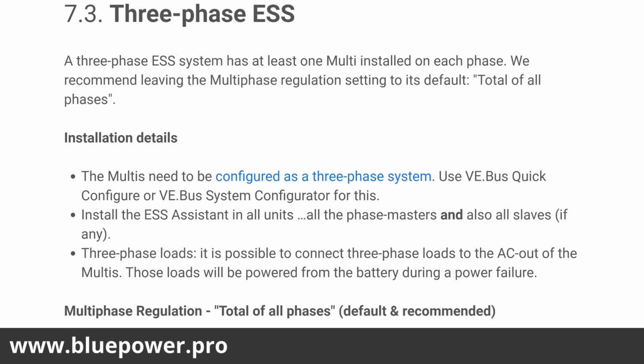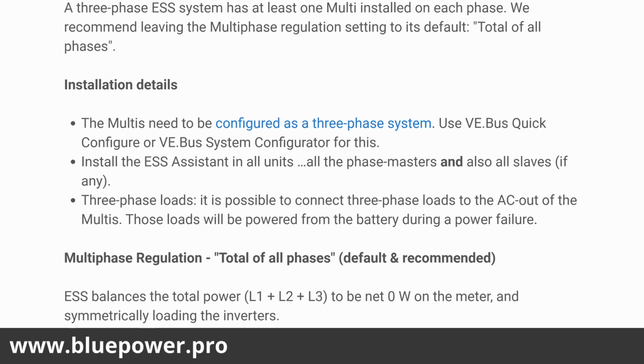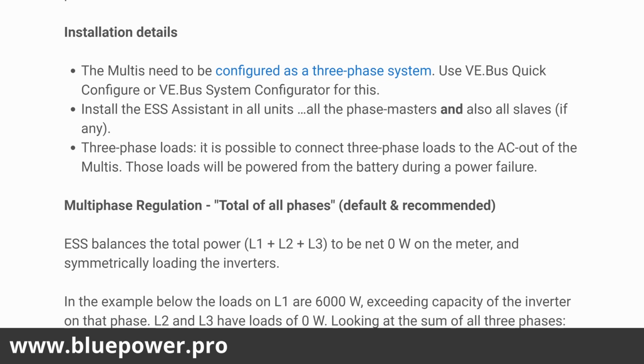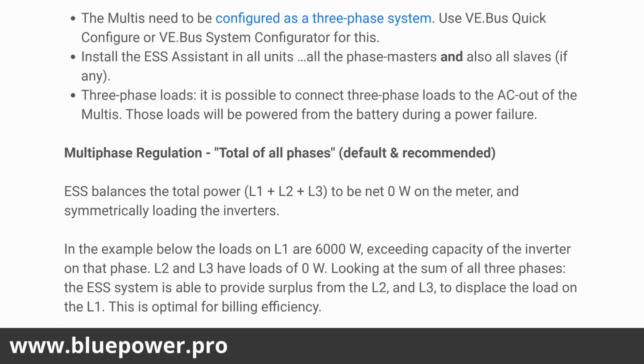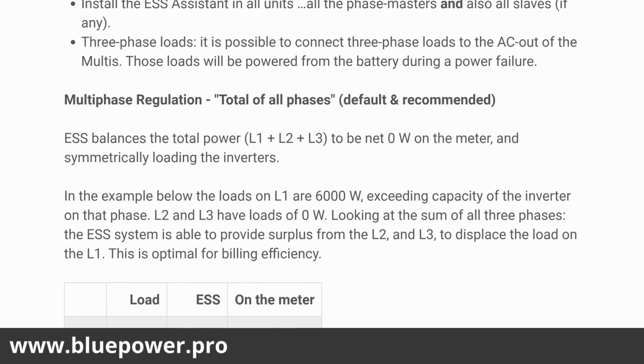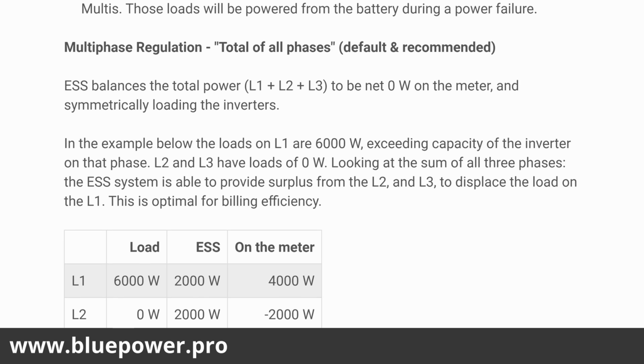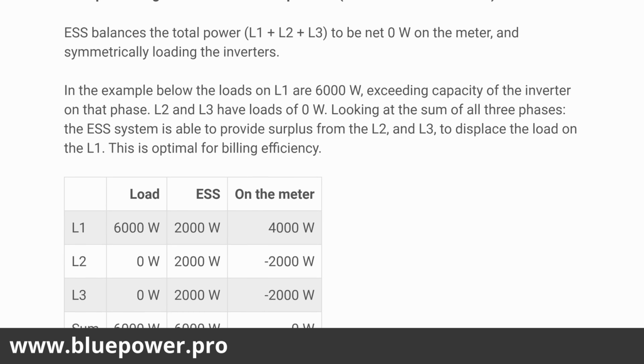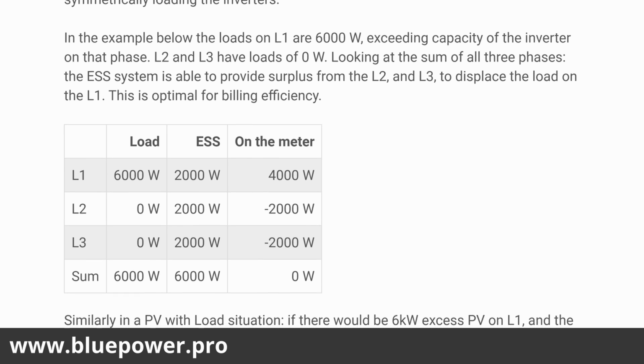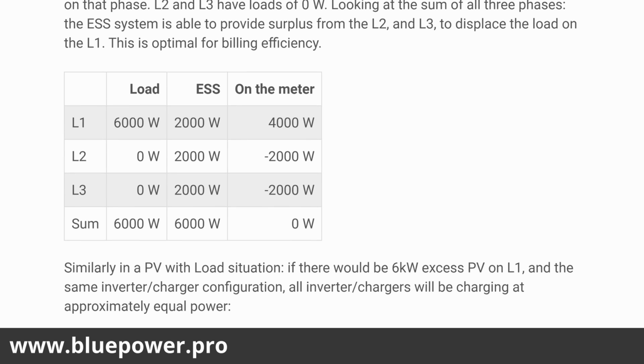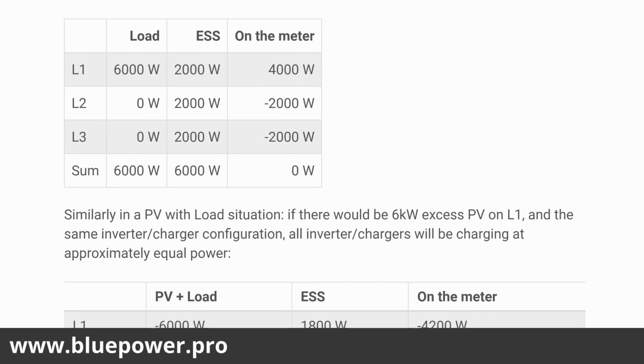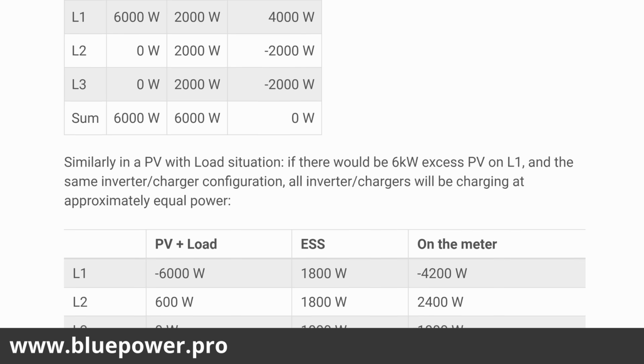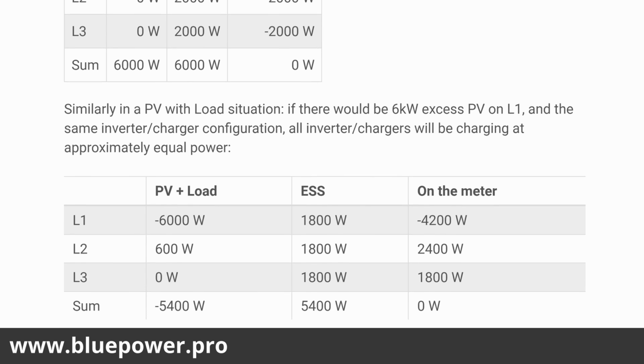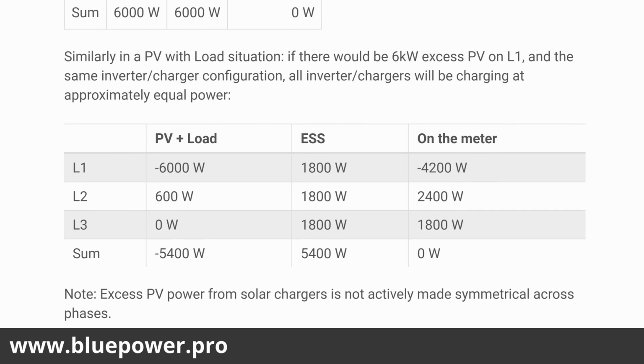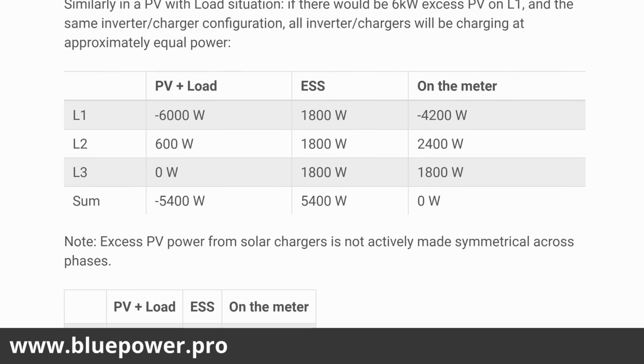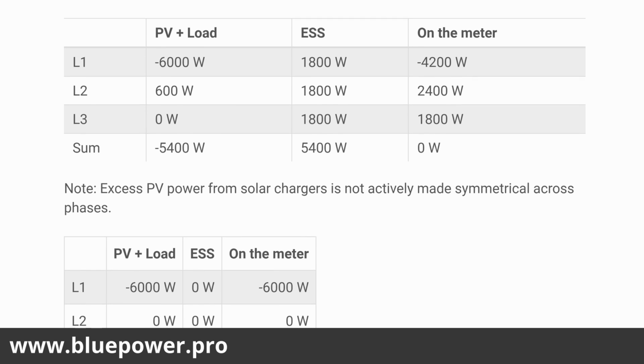And then on some meters that can cause excess billing due to the feedback that it measures. And then you draw in another power again, so it double bills you for the power that you consume. So make sure that if you've got an electronic meter, that you've got the multiphase regulation selected on per individual phase. Here's our minimum SOC unless grid fails. That's just the minimum state of charge that this system is going to use for solar or self-consumption. And then if there's a power failure, you're going to use the rest of the battery capacity if you're already sitting at your minimum level.